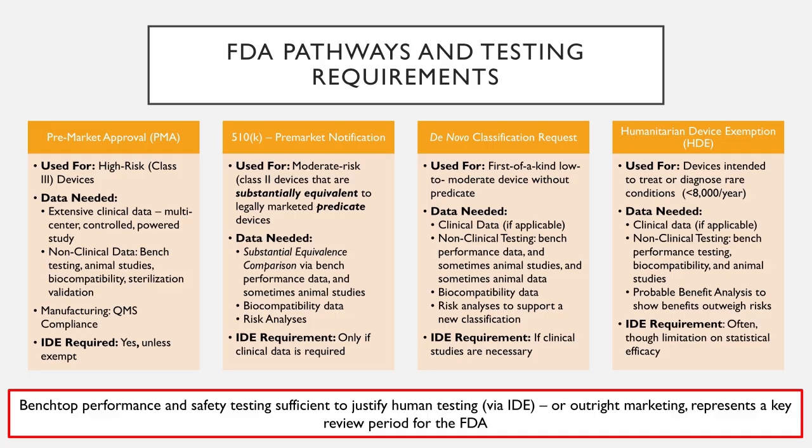Usually it's a huge milestone to go from that preclinical setting, that benchtop testing and animal setting, to then graduate to any potential necessary clinical testing that might be required. Or the testing that will otherwise be required to get the IDE in the first place might be all that you need in order to actually get clearance or approval, like in the case of the 510(k) pathway, or maybe the de novo classification or HDE pathway, where you might not have to do clinical trials at all. The data that you would otherwise need for that IDE represents that clearance or approval pathway in itself.